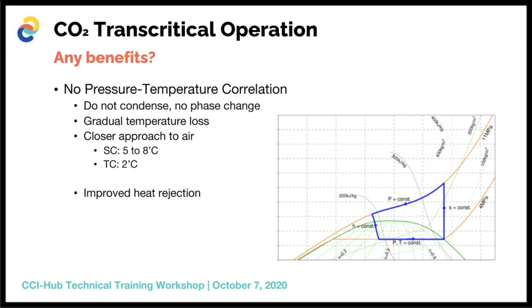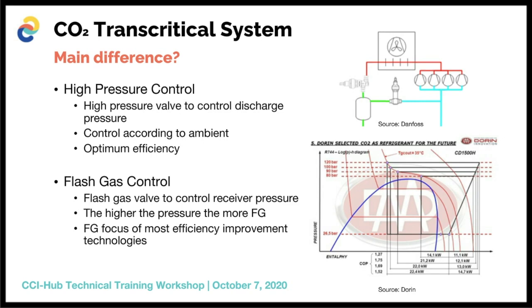Then what are the main differences of a CO2 transcritical system? Because overall, a basic CO2 transcritical system operates on the same parameters or same aspects as you would find in a normal centralized Freon system with direct expansion. So the main difference only comes in with the high pressure control and the low and the flash gas control. So your discharge pressure being at a higher pressure than what we will see in conventional refrigerants needs to be released to a lower pressure, and especially when operating in the transcritical mode, you need to take your refrigerant that's in a gas phase and expand it into the two-phase area so that you can create liquid. While creating liquid, you're also creating vapor, and this means that you basically need to take care of that vapor and take it back to a compression cycle.